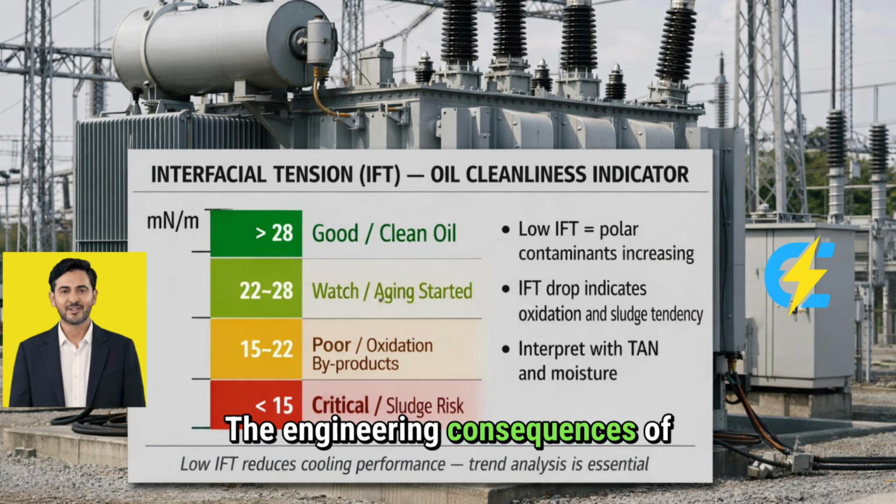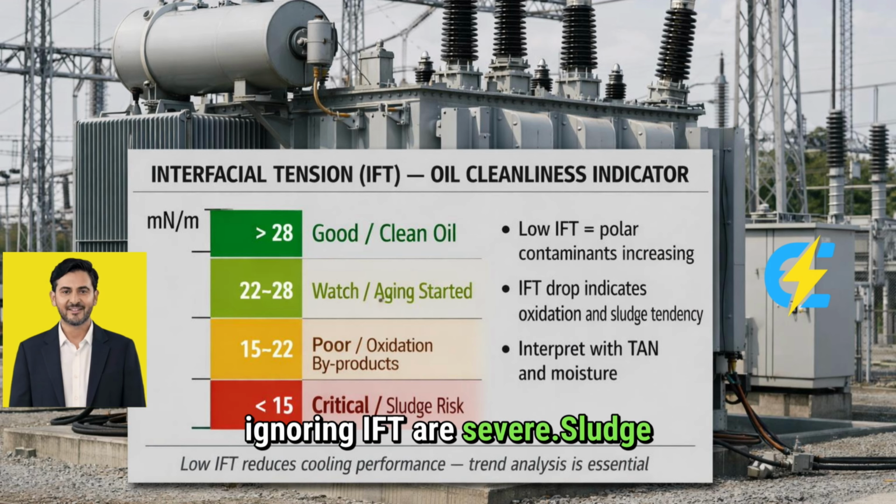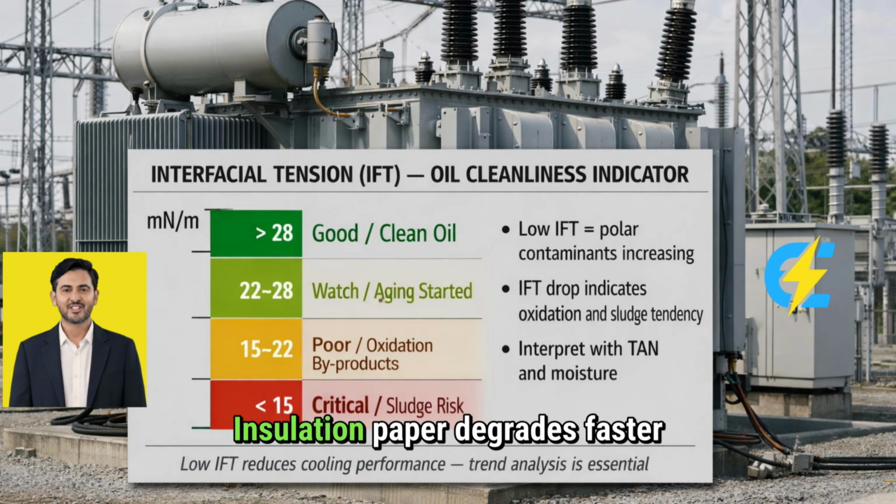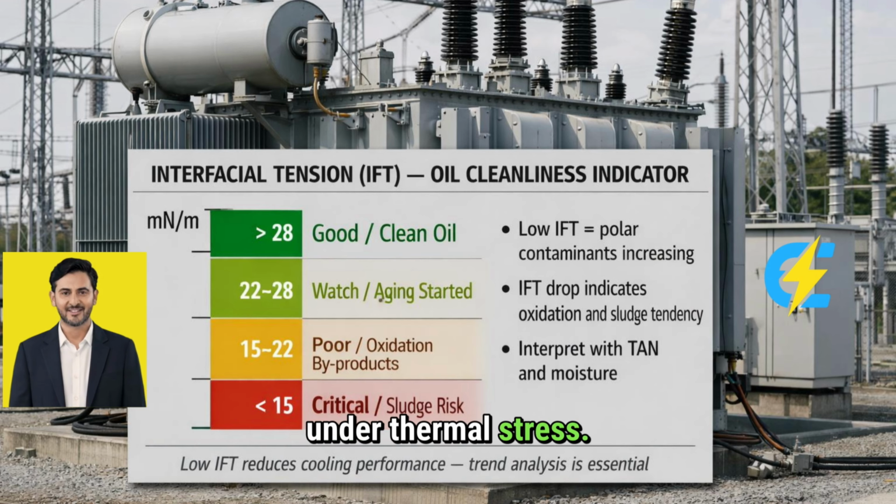The engineering consequences of ignoring IFT are severe. Sludge deposits block cooling channels. Hotspots develop. Insulation paper degrades faster under thermal stress. Moisture absorption increases. The transformer's life expectancy drops dramatically. What should have been decades of reliable service becomes years of mounting problems.